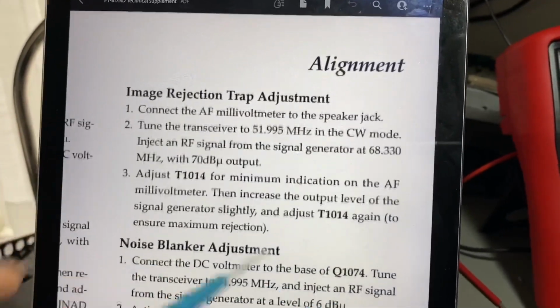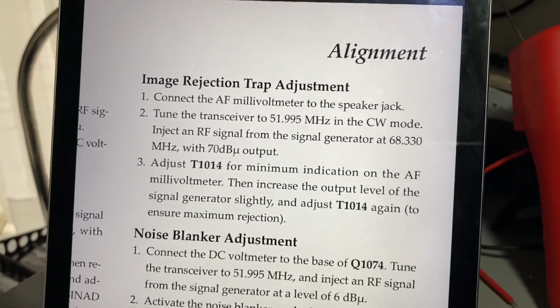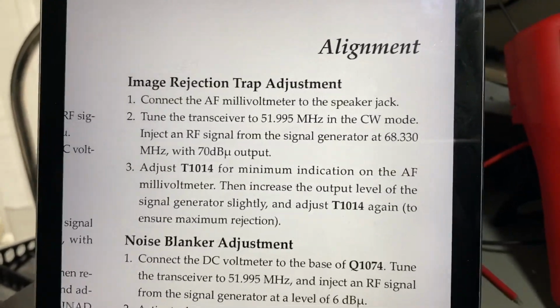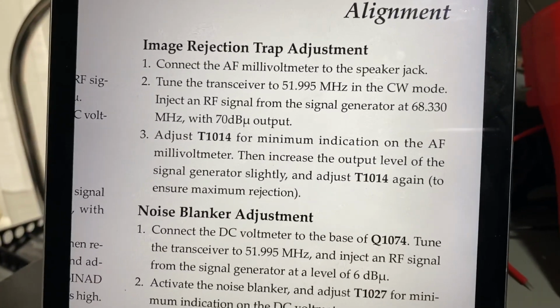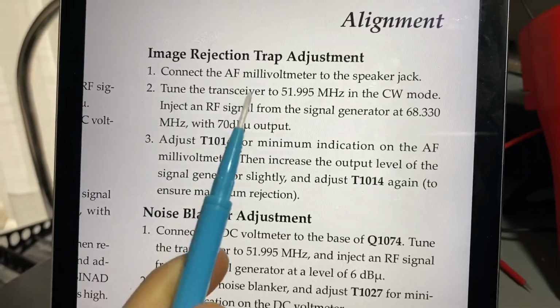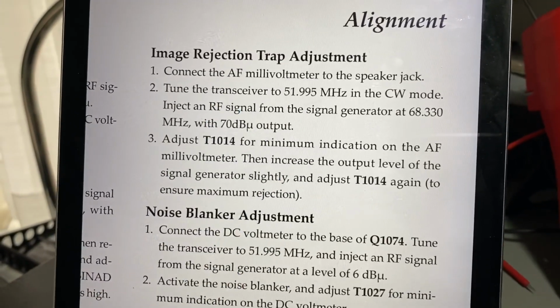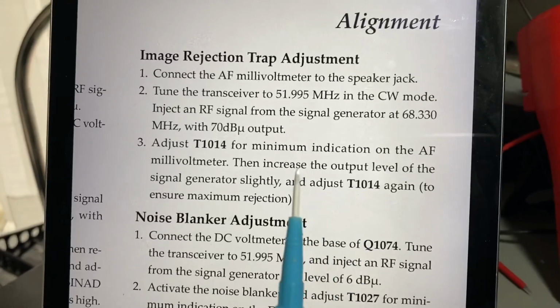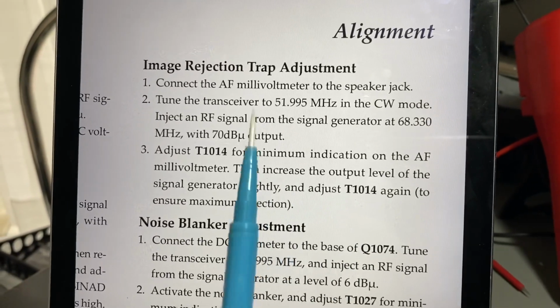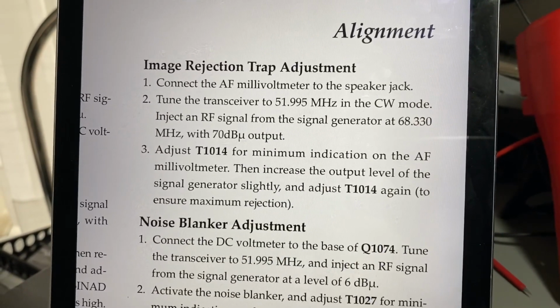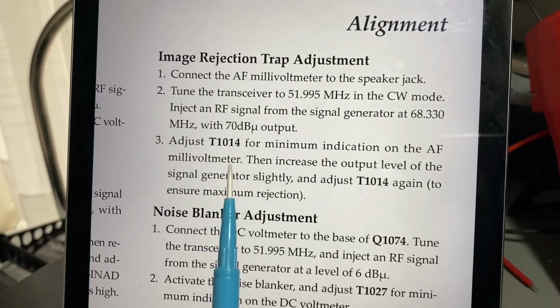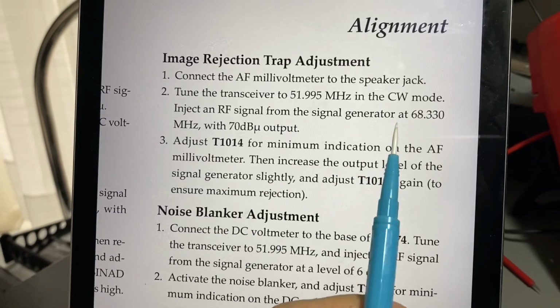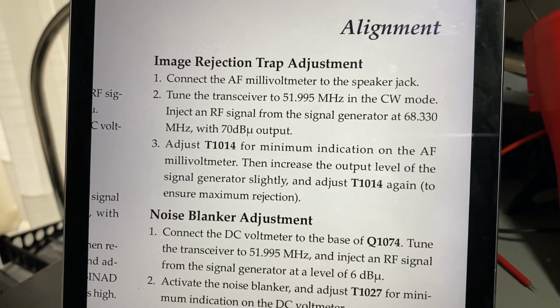Now the next one is image rejection, for the rejection of the image frequency. It says to connect the speaker to the audio millivolt meter, tune the transceiver to 51.995 CW, and inject a signal at 70 dB microvolt on the frequency of the first IF.